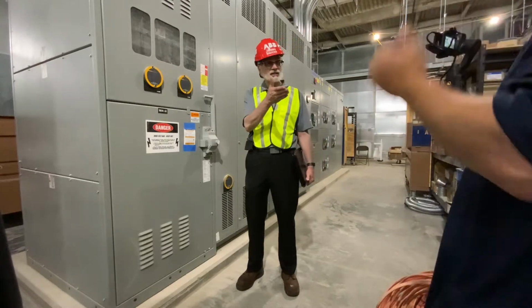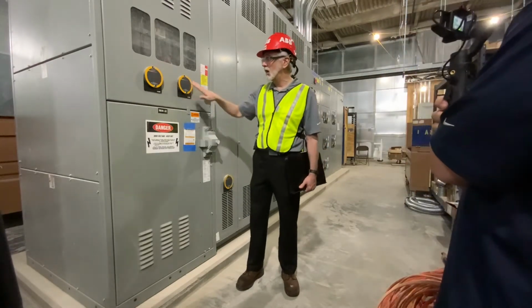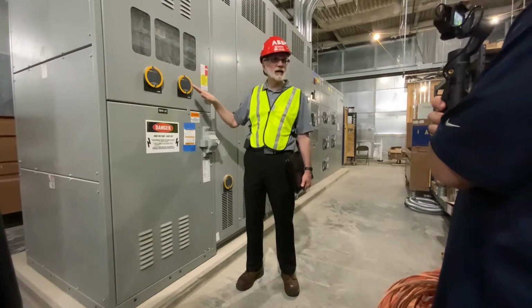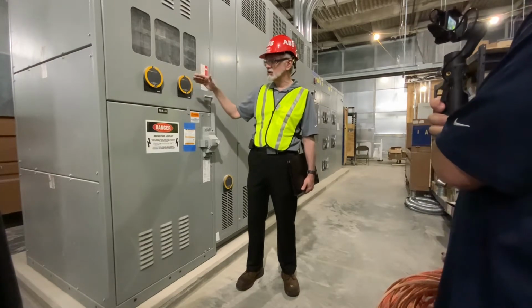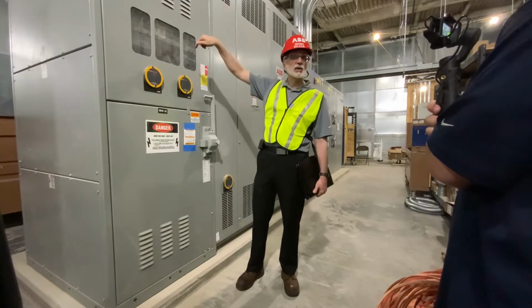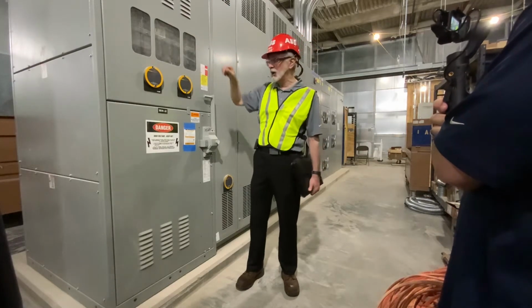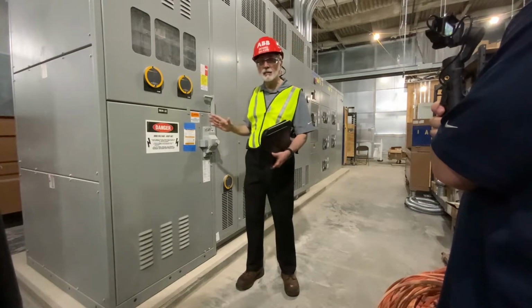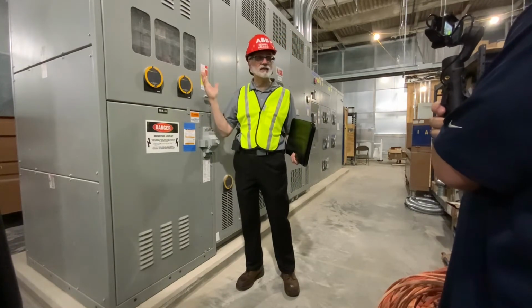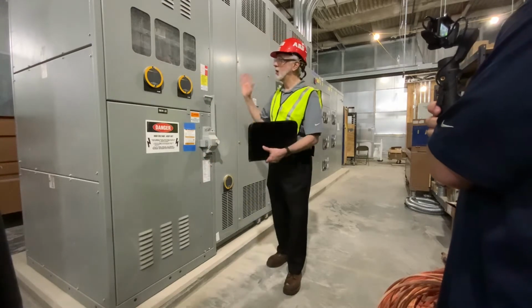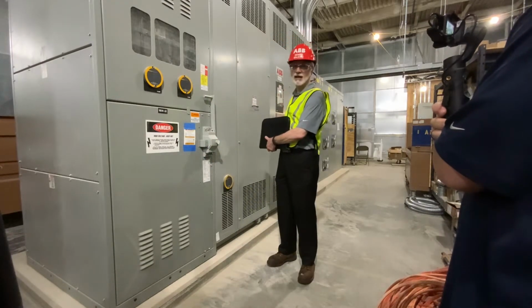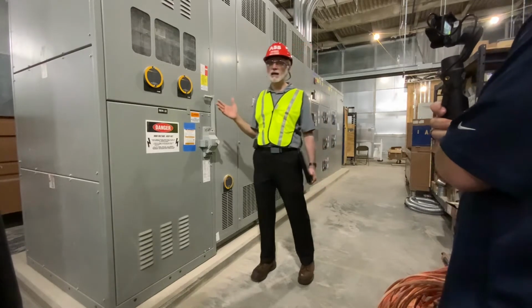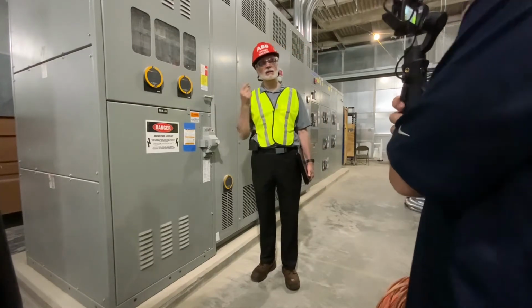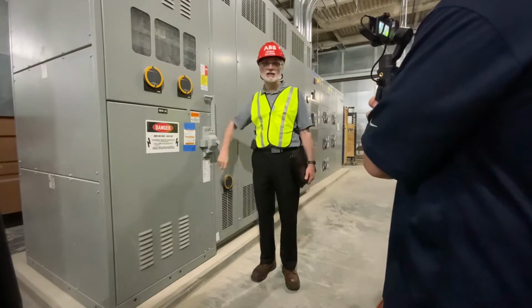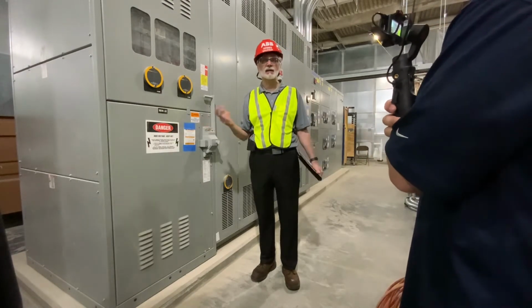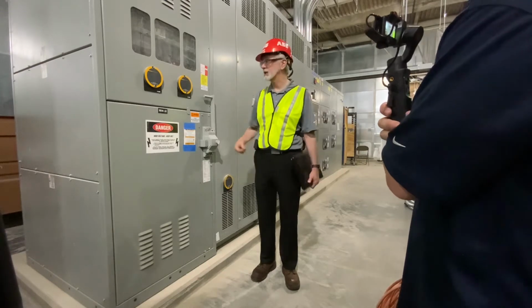From a cable connection standpoint, like we talked about downstairs, there are a set of infrared sights here so that you can go in and look at the switch here in the front, and then also I think we're going to see there's a set of IR ports in the back. Again, very basic operations. It's just an on-off device with a set of fuses whose primary function is to protect the transformer. From a service and maintenance standpoint, keep it clean, use vacuuming, and exercise the equipment annually if you have the opportunity. Every other year, you can probably stretch that out too.